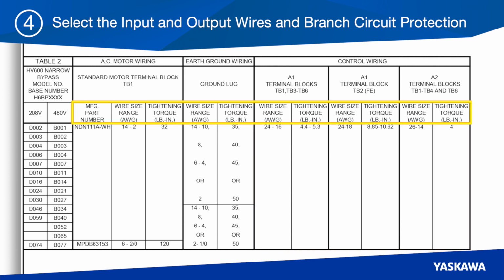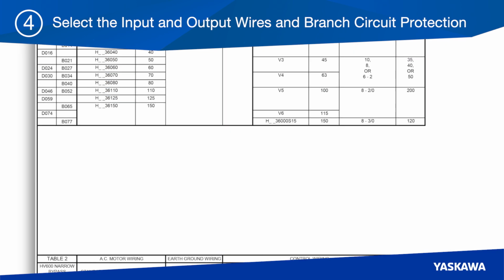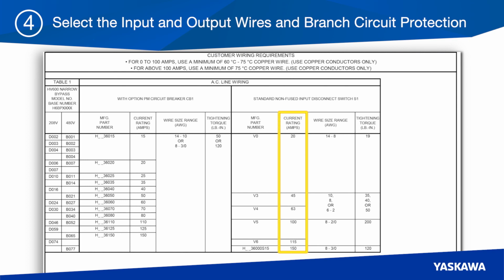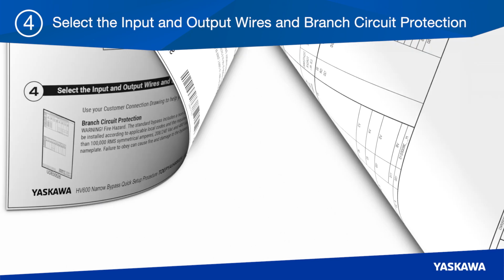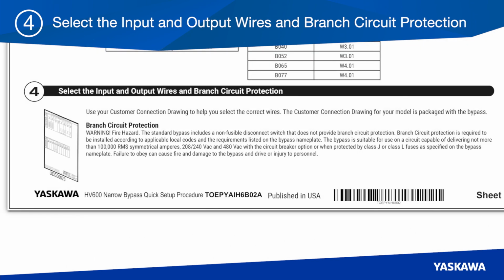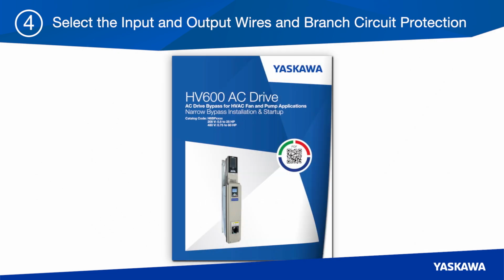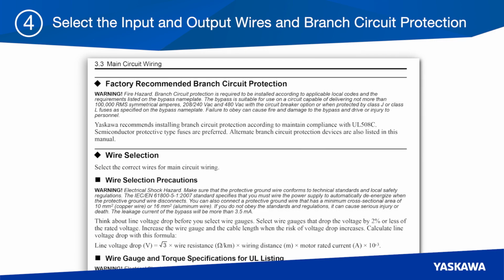Information on wire size and clamp-down torque settings are also listed on this drawing. Be sure to use the correct terminal torque settings for your model size as indicated on the connection drawing. Current ratings for the disconnect switch and the optional circuit breaker CB1 are shown on the customer connection drawing. Yaskawa factory recommendations for branch circuit protection are located in Step 4 or the main circuit wiring section of the installation and startup manual.